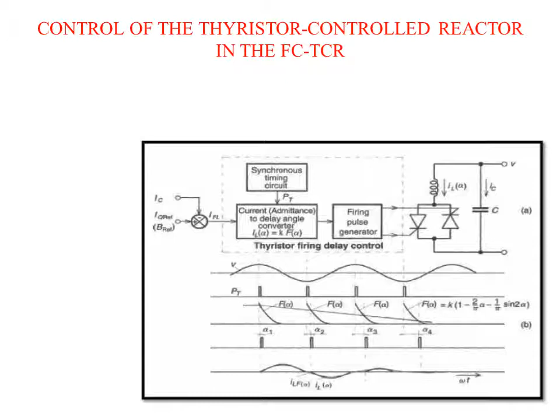One function is synchronous timing. This function is usually provided by a phase lock loop circuit that runs in synchronism with the AC system voltage and generates appropriate timing pulses with respect to the peak of that voltage. As we have seen in the first figure, the static var compensators are connected in shunt to the extra high voltage line, and that line is AC in nature and sinusoidal. So we have to convert the sinusoidal signals into discrete form, and this discrete form of voltage and current can be generated using a phase lock loop, which is the synchronous timing circuit.